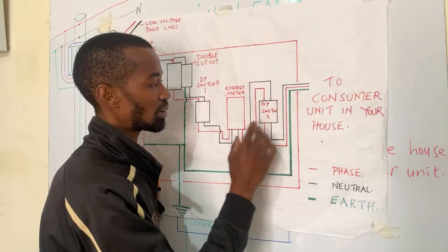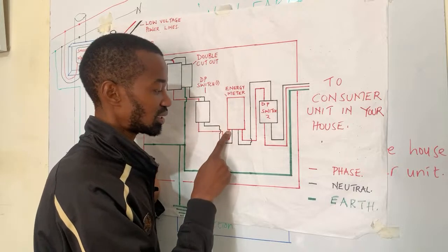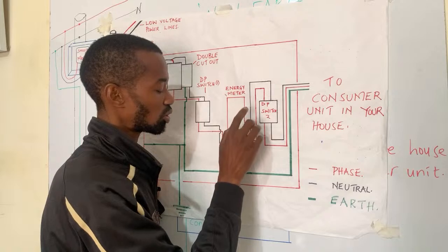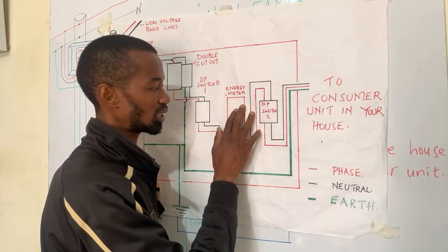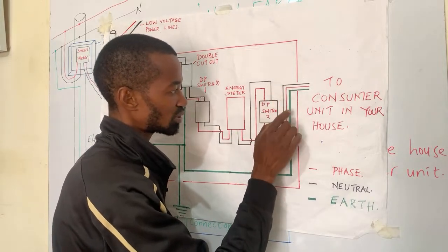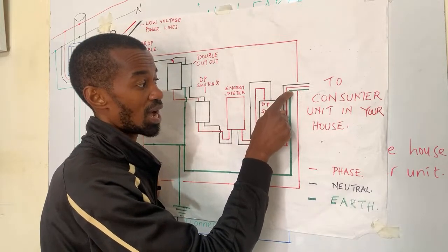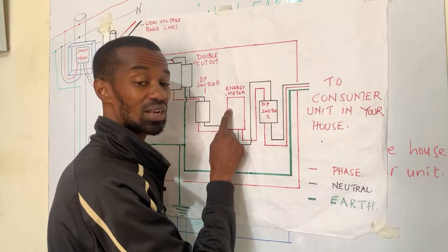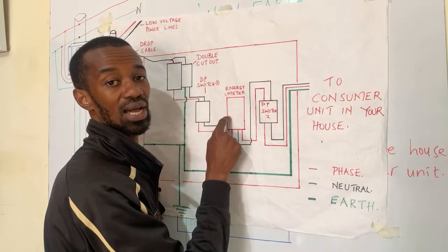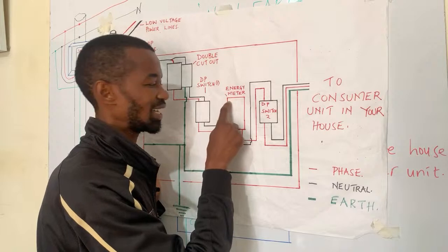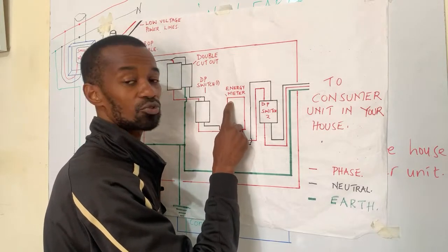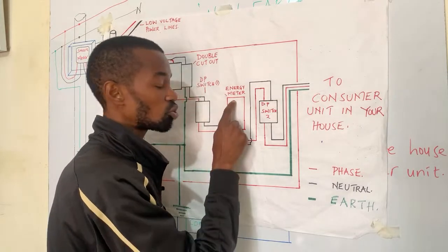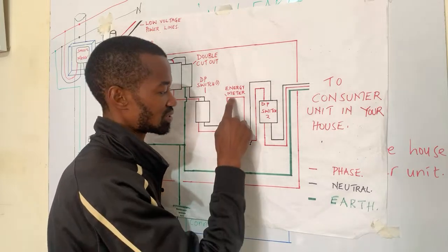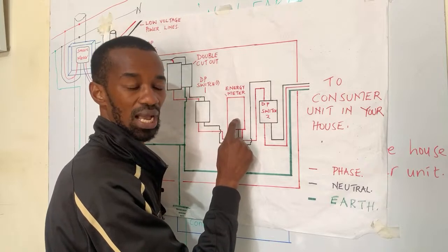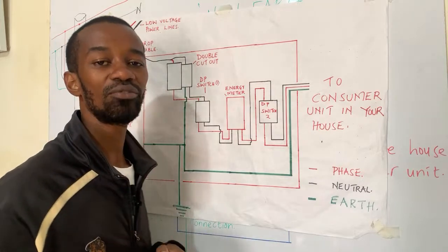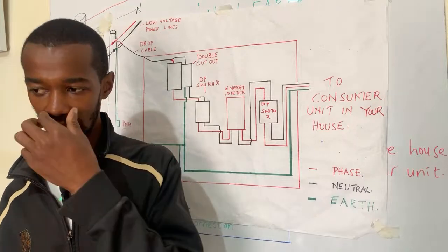So if you find that there is a bypass, it means that this energy meter will not be giving the correct readings, meaning that it will be consuming a lot of tokens or units. Therefore, you are supposed to do what we refer to as a separation between the neutral and the earth connection, because this energy meter will even get to a point whereby after the tokens get to zero or they are consumed, it will start recording a negative, so that if there is -2, -3 units, you will have to pay for those units, and they usually get consumed very fast, so that you pay until it indicates zero, and then from there you can buy units. That one is usually very detrimental to the user, because you are charged extra.